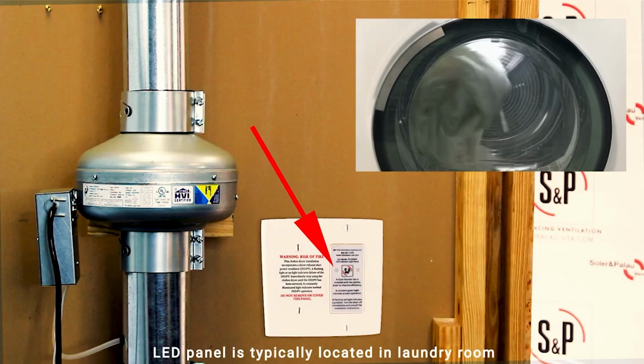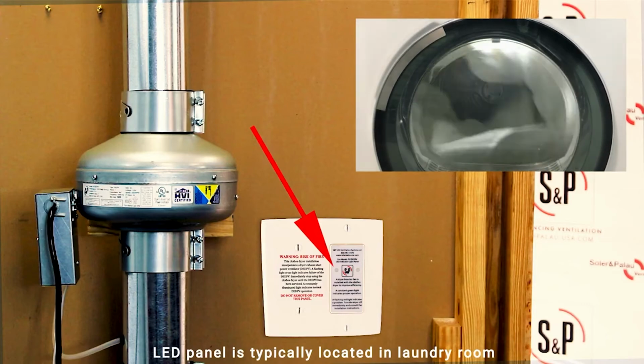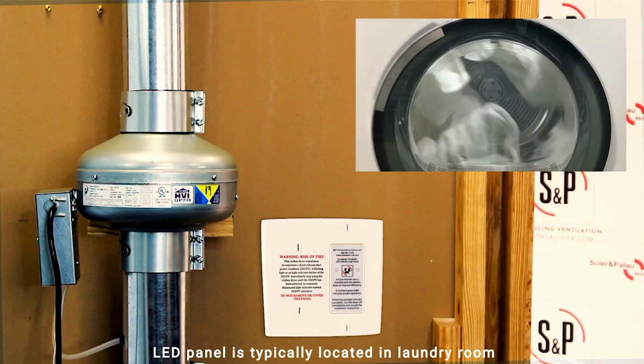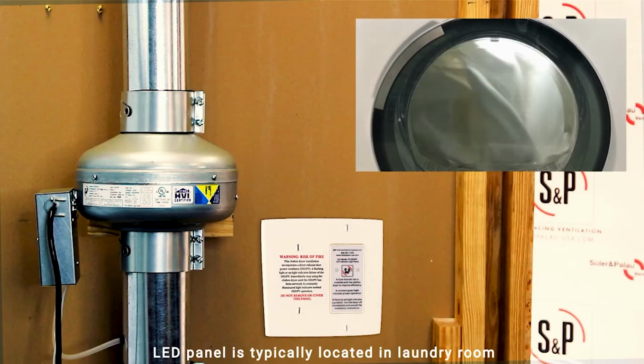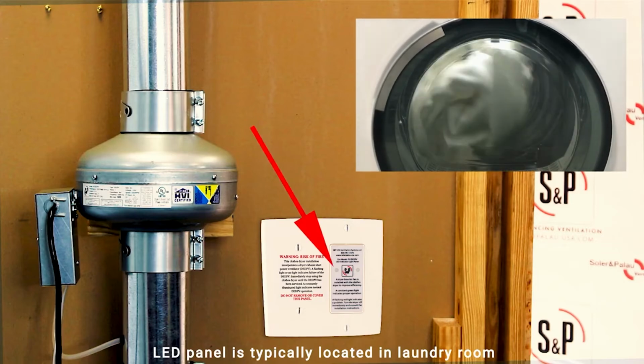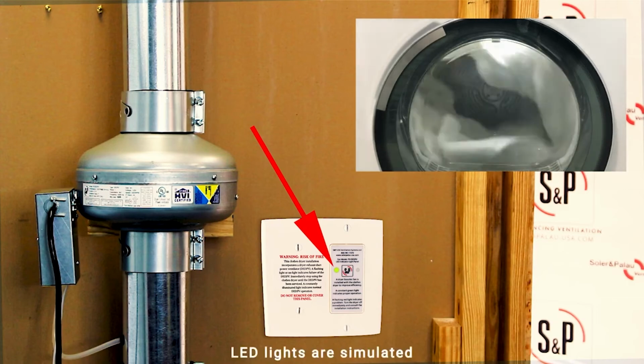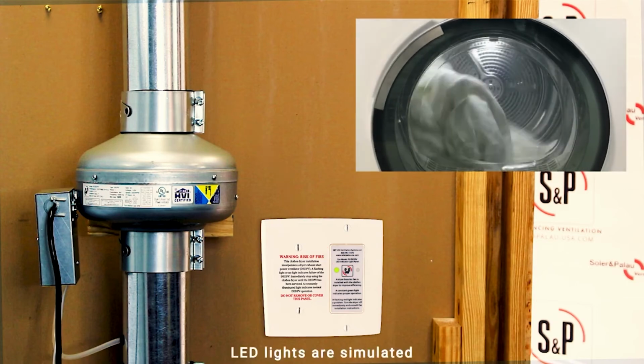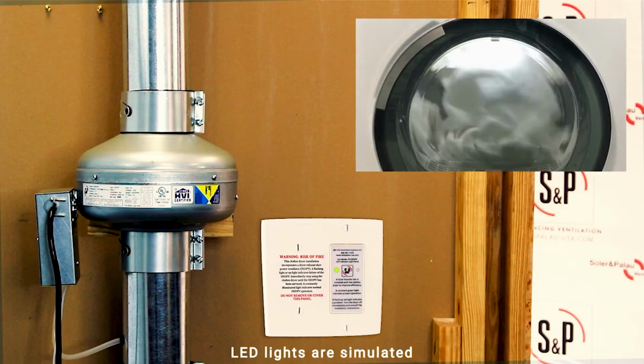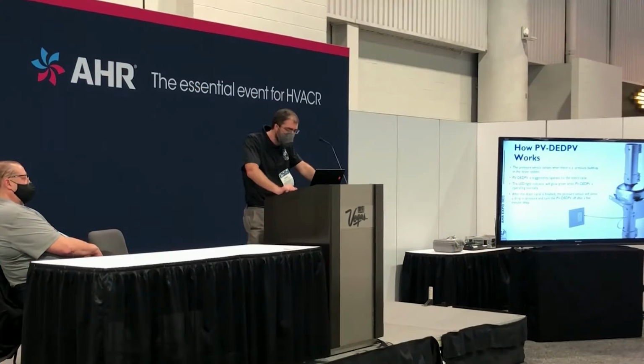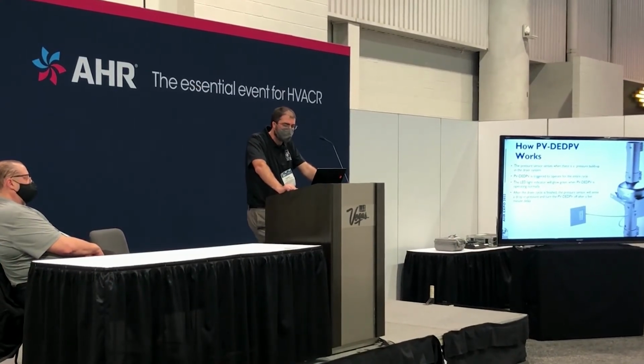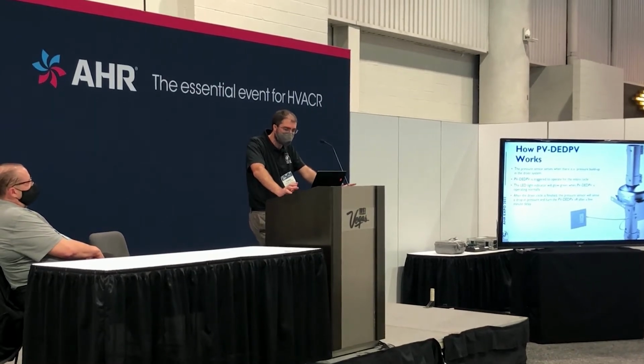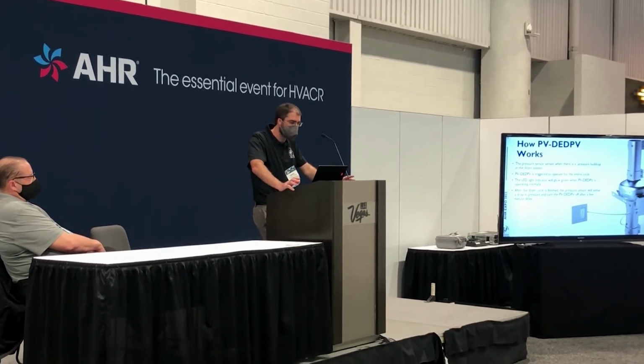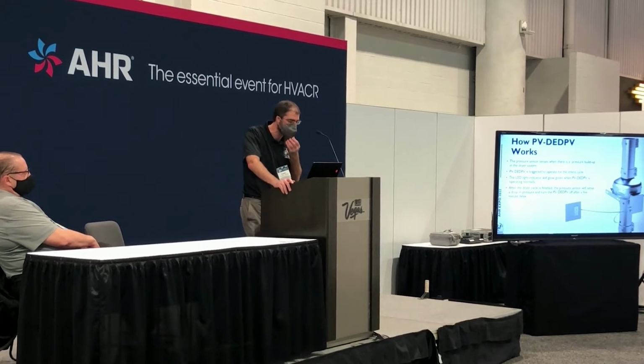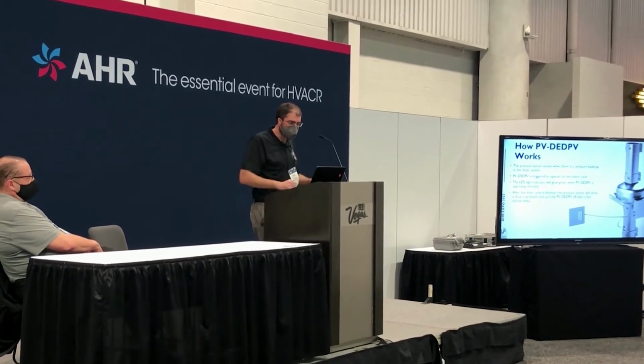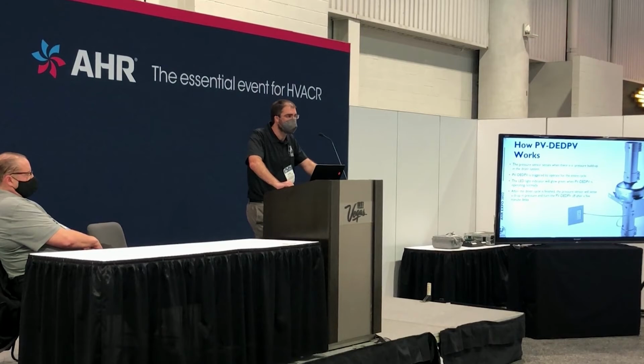The LED light indicator is the next feature, and it will glow green when operation is in normal range. Conversely, the LED will flash red in sequence, indicating abnormal operating conditions, such as lint blockage in the ductwork, lint buildup upon the impeller, and excessive temperatures over 196 degrees Fahrenheit are all possible abnormal operating scenarios.